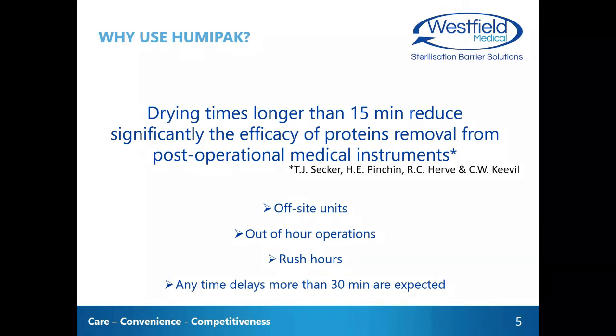A lot of operations are done, especially in some smaller units, during nighttime and weekends when the CSSDs are not operational. HUMIPAK is a very good solution for these units. There are always rush hours when there are delays and the surgical instrument trays will be sitting longer than 30 minutes before they get reprocessed. In quite many countries, 30 minutes is kept as a guideline: if surgical instruments need to sit for 30 minutes or longer before they get reprocessed, they should be kept in moist conditions. Therefore, any time there are delays expected of more than 30 minutes, use of HUMIPAK may be a good idea.